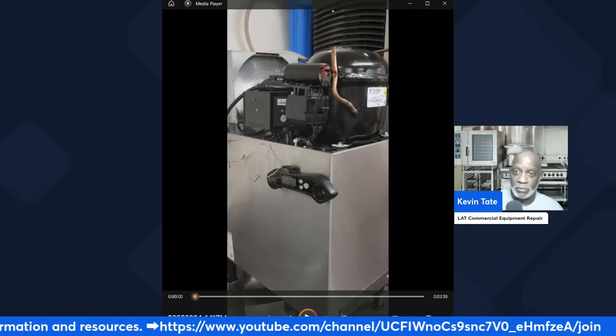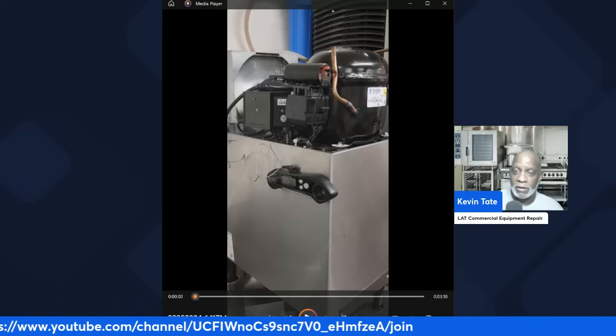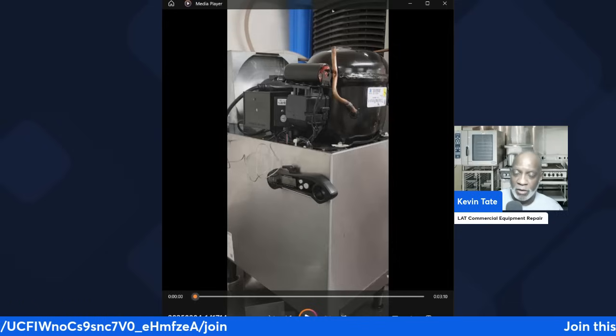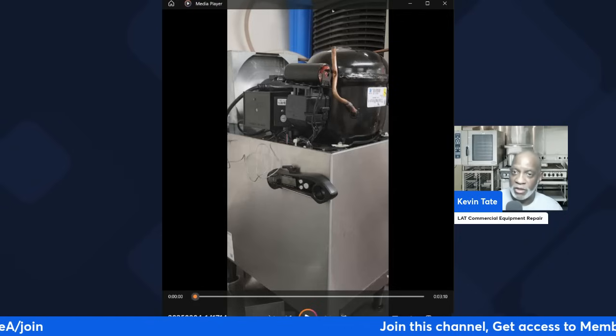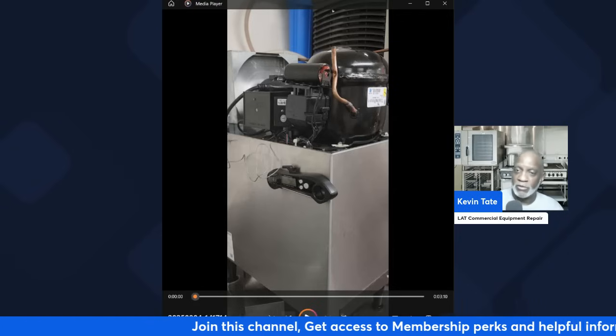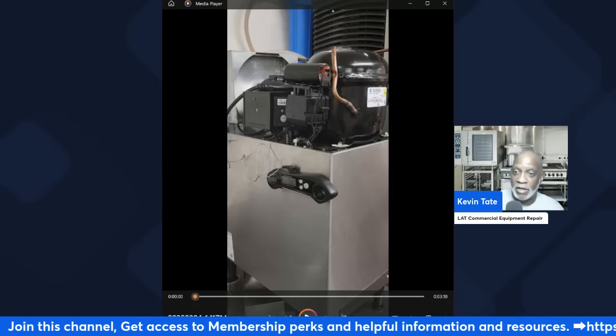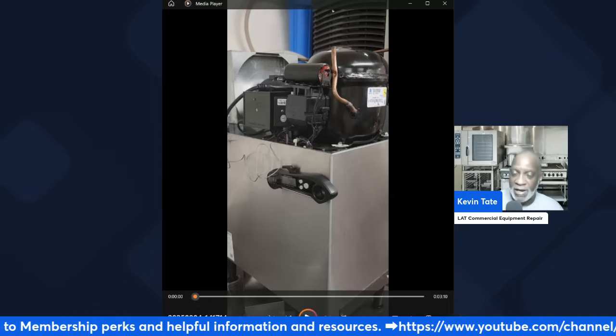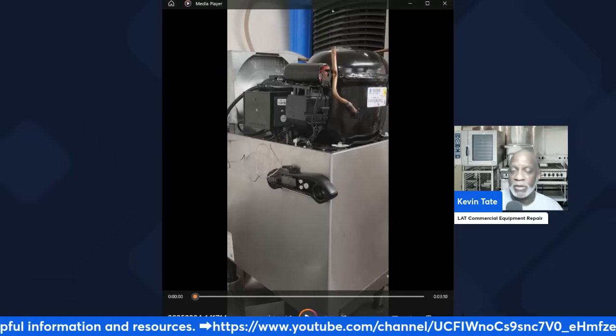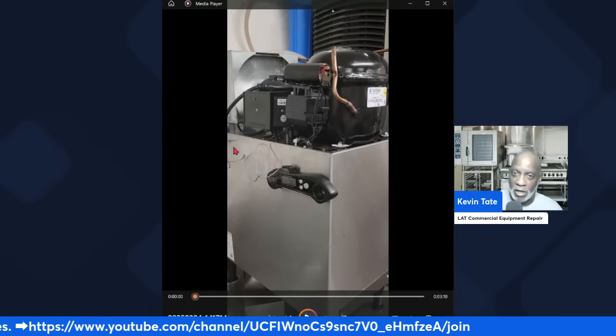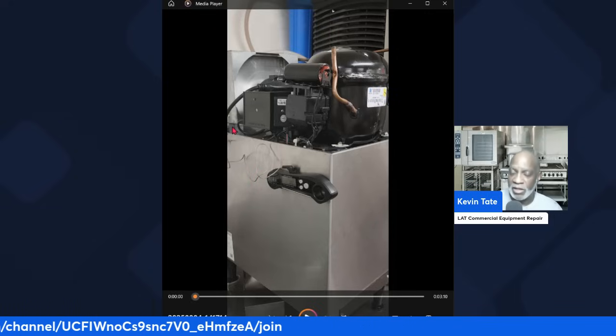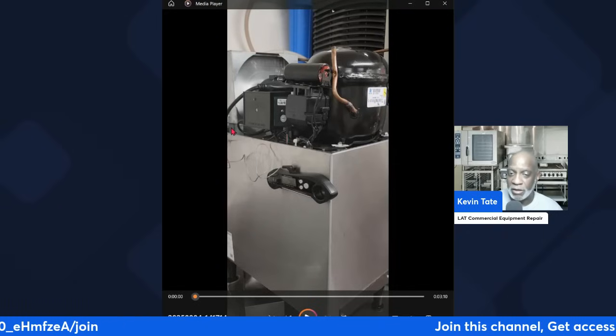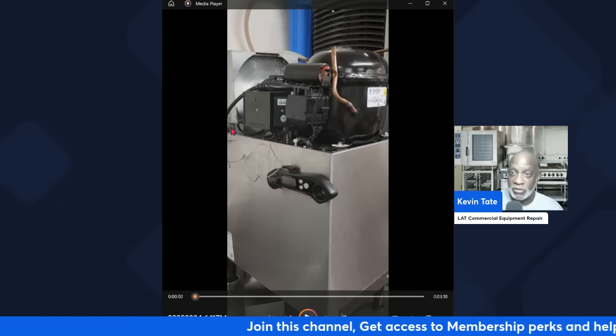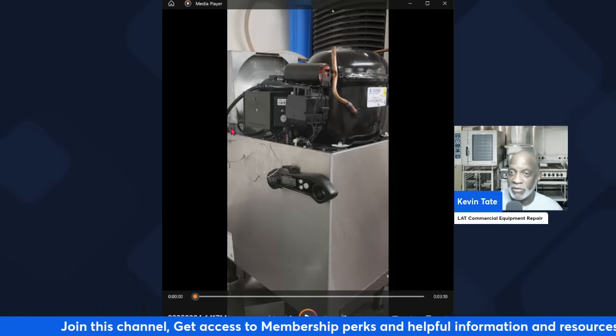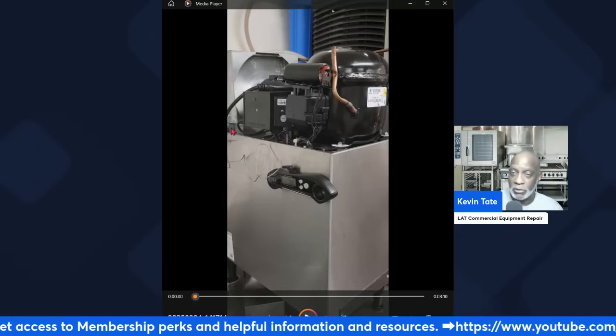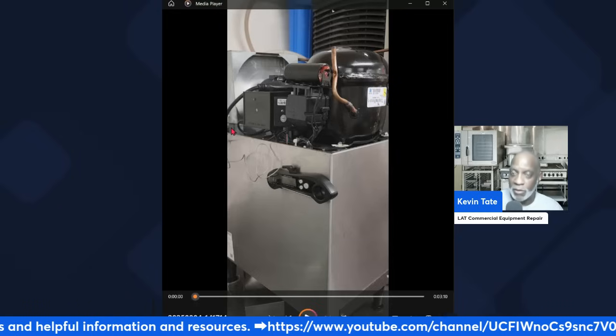So that's a quick overview on the Lancer 500 model chiller machines. Like I said, these machines are great, and they work off of a bar gun system. If you ever get a call that the chiller's not freezing on these 500 systems, the best thing to look for first would be to pull it out some so you can get to the back, then look down in that slot behind the condenser coil and see if the water bath is empty. If that water bath is empty, you'll want to fill it first, then allow it to freeze down.